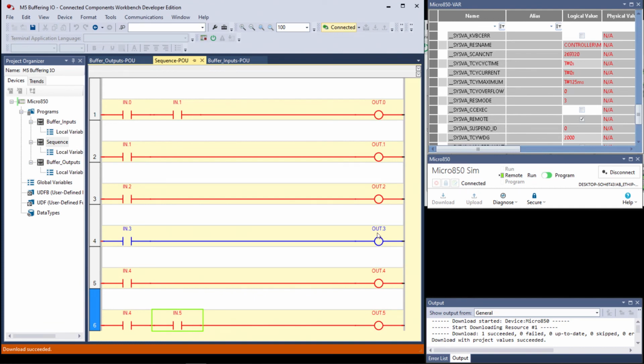All instructions are either conditions or actions. Conditions are always true or false, never on or off. Now you can look at this. This is a true if on, and you can look at its state and say, oh, that must be on. That bit is on in memory. But that's not what this is saying. It's only saying it's true. It's the fact that you can read it as a true if on, therefore, if it's true, then that has to be on. But these are all true and false over here.